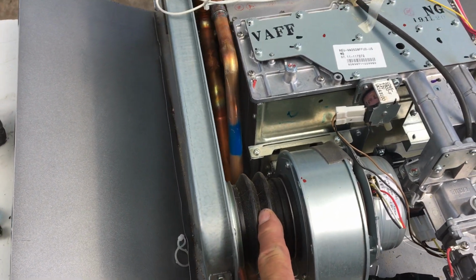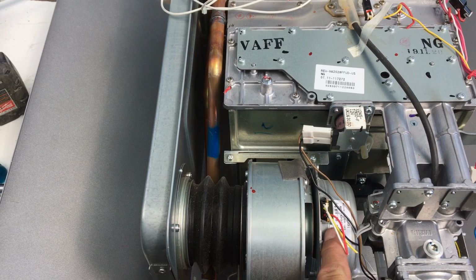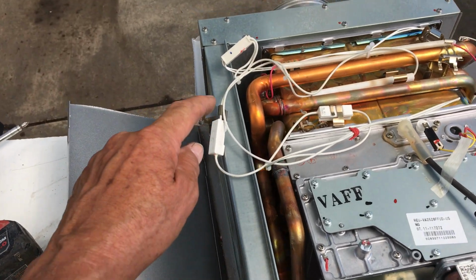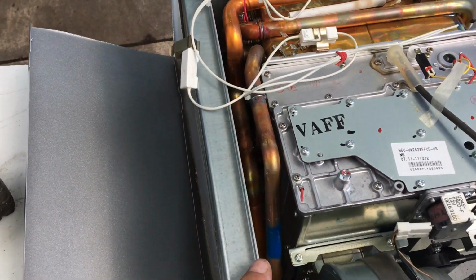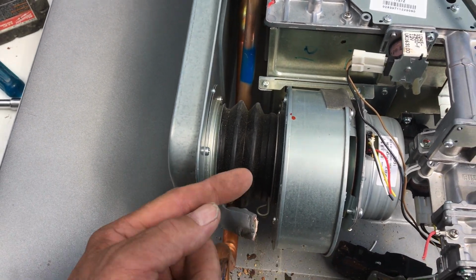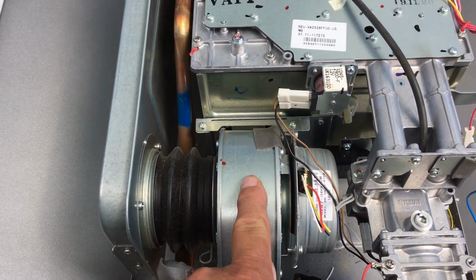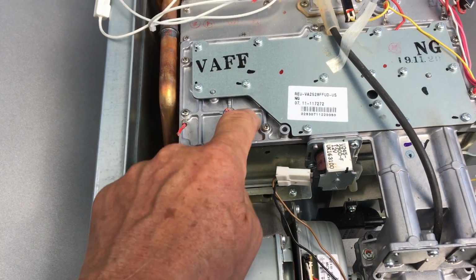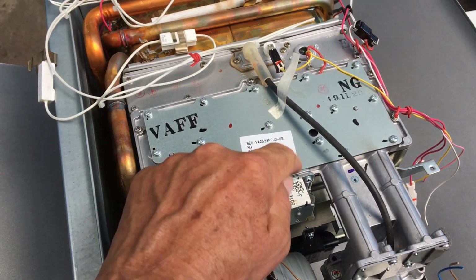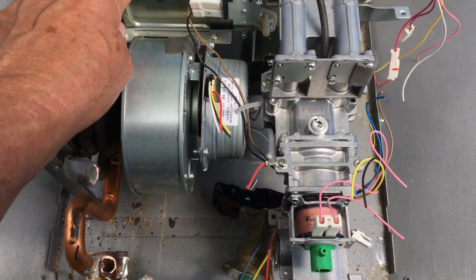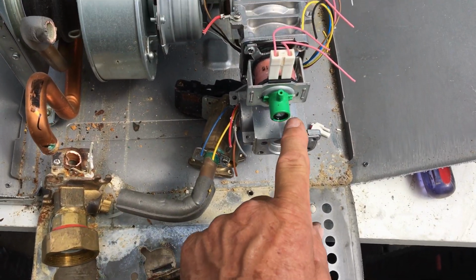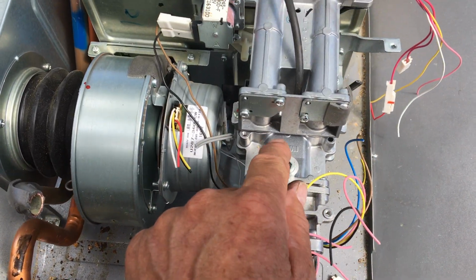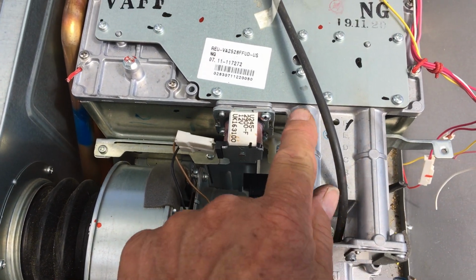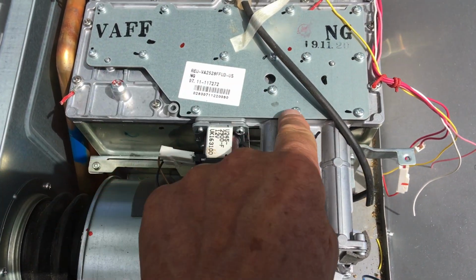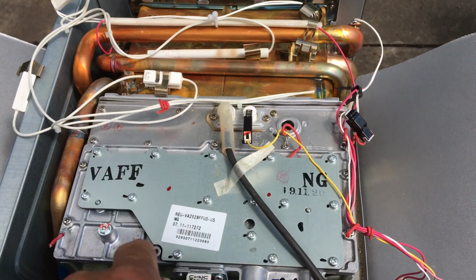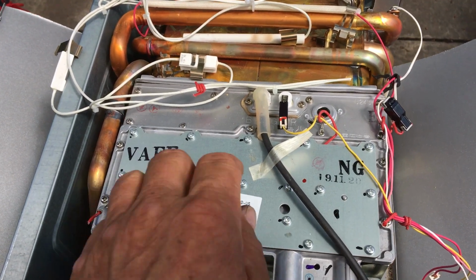This blower is a little different than some of the boilers we work on. It looks like it brings the air in, blows it through the blower, and then out of the blower up into this combustion chamber. The gas comes in here, goes through the gas valve, and then it is also injected up into this combustion chamber. So I think the mixing of the air and the gas happens here.